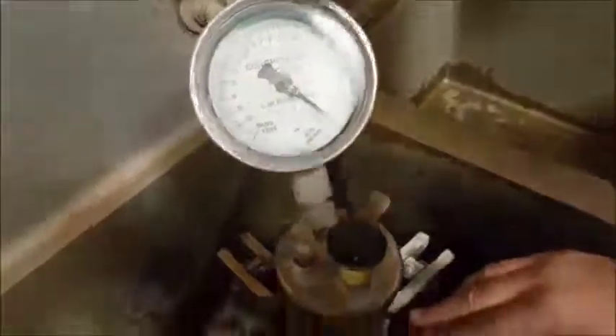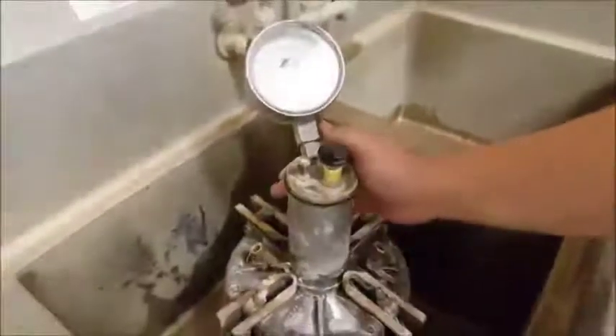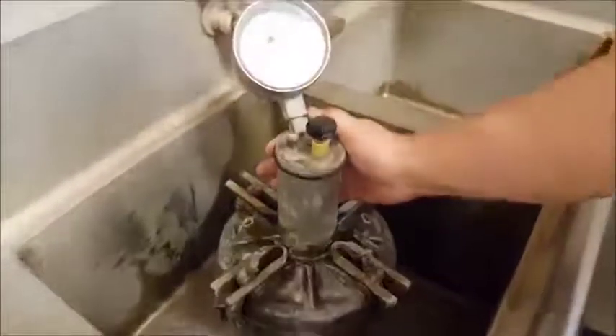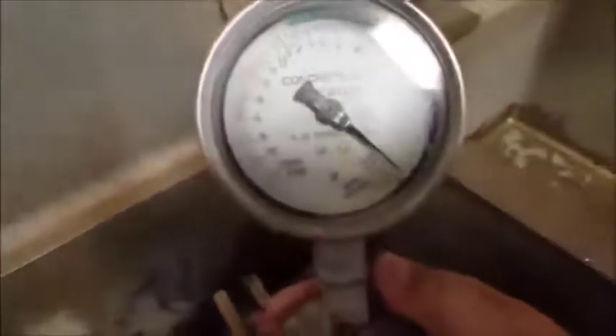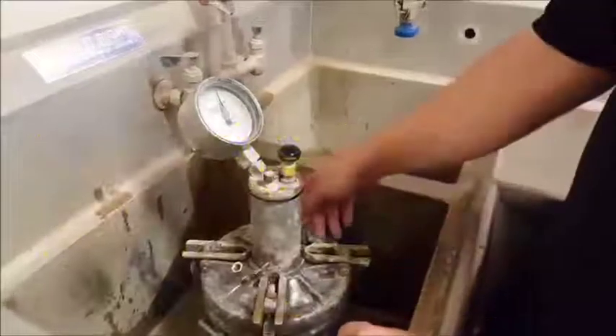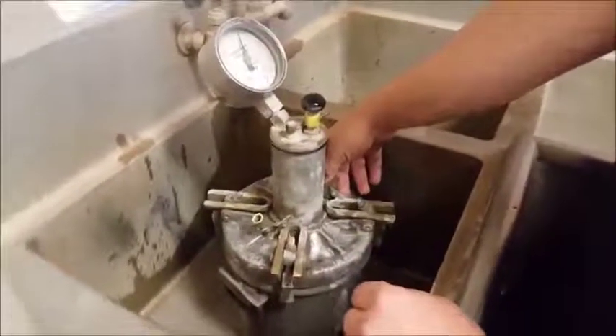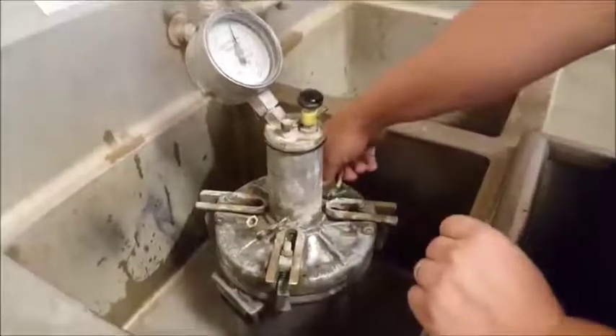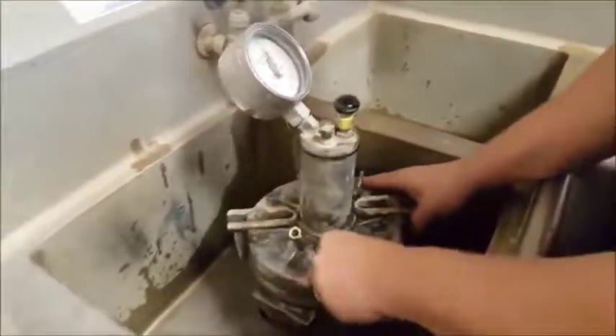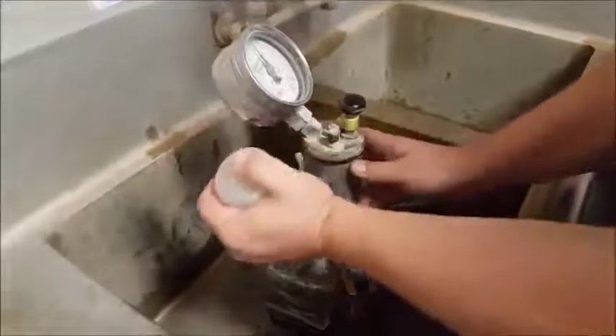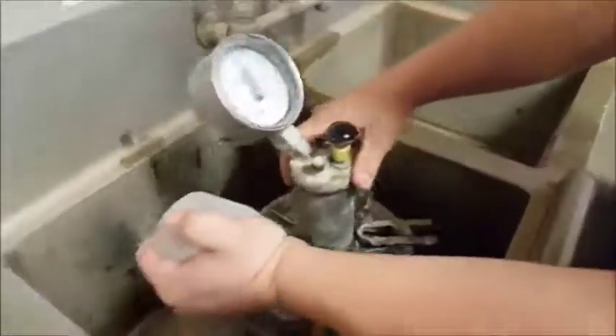Okay, we're going to close the petcocks and release the pressure, and that should stop on the 0. If it stops on the 0, you know your initial pressure was set correctly. Next, we're going to release the pressure out of here, opposite side of where the tube was. We'll open both of these up. We're going to make sure this is filled back up again. Get all of those air bubbles back out.